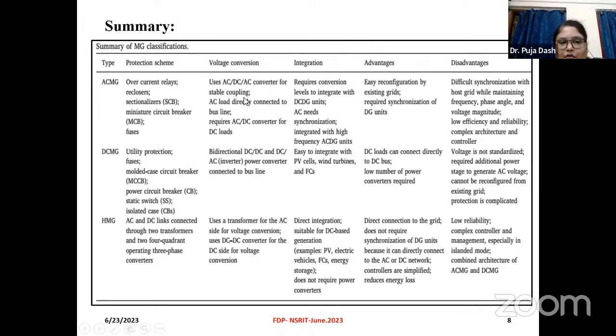So whenever talking about voltage conversion in AC microgrid, it uses AC-DC-AC converters for stable coupling, with AC load connected directly to the bus line. This requires AC-DC converters for the DC loads. When talking about DC microgrid, bi-directional DC-DC and DC-AC inverters are used, with power converters connected to the bus line.